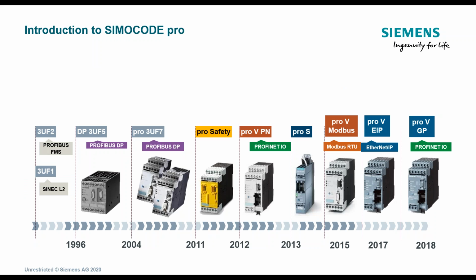SIMOCODE has been around a while. This is not just a new product. Here's kind of the genealogy of the product. You can see that it started back in 1996 as a Profibus DP. It only spoke Profibus. One key I want to point out with the older system is that it had an integrated CT in it, meaning that the current transducer, the current measuring device, was all one piece with it.